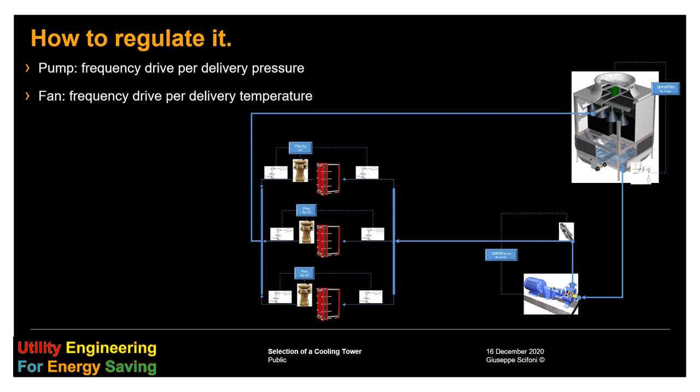A couple of words concerning the regulation. Actually, it depends upon the circuit. Let's take a very simple one, a single loop. Typically, the users are provided with flow control valves, like in this case, to keep constant flow rate across the heat exchanger. In this case, we need just to provide a constant pressure before the users, by means of the frequency drive of the pump.